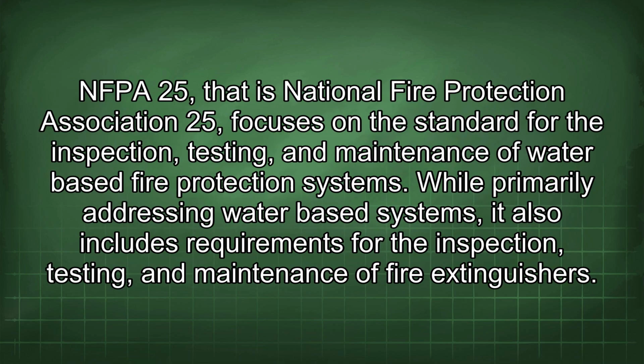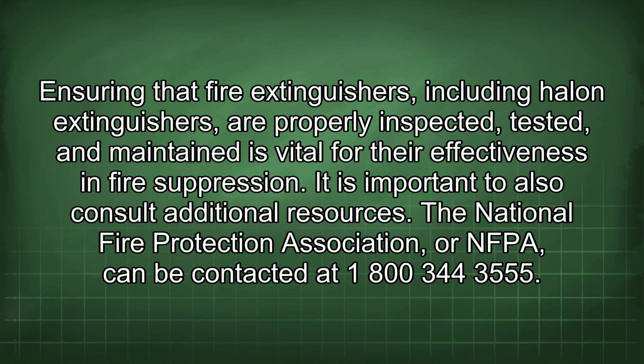NFPA 25, that is National Fire Protection Association 25, focuses on the standard for the inspection, testing, and maintenance of water-based fire protection systems. While primarily addressing water-based systems, it also includes requirements for the inspection, testing, and maintenance of fire extinguishers. Ensuring that fire extinguishers, including halon extinguishers, are properly inspected, tested, and maintained is vital for their effectiveness in fire suppression. It is important to also consult additional resources.